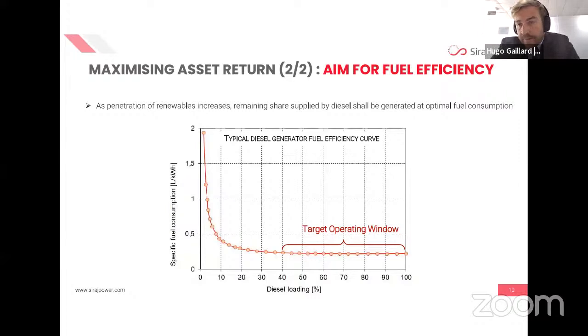Which means that if a generator at a certain point of time is oversized compared to the load demand, let's say the net load demand, so the load demand minus whatever is provided by solar or by the battery, we need to make sure that at this point of time, the loading of the genset is not too low. And for that, we use different sizes of generators. So contrary to what we commonly see as a baseline, where we would have a set of similar gensets, we try to keep different generator sizes in order to be able to switch on and off the right generator at the right moment.